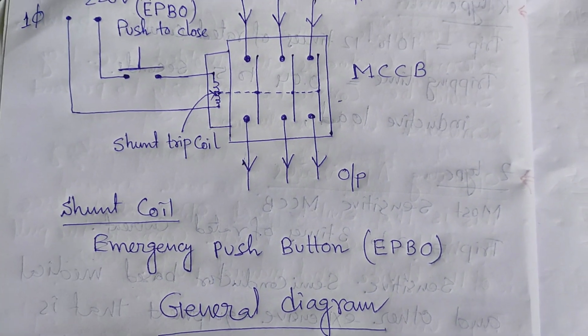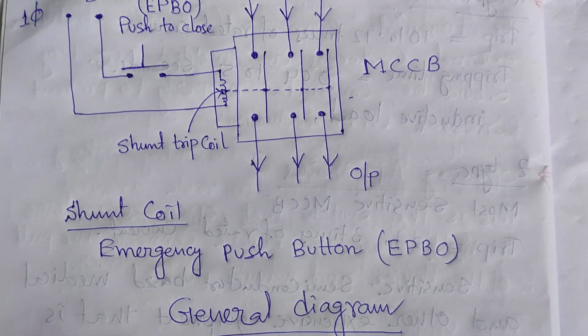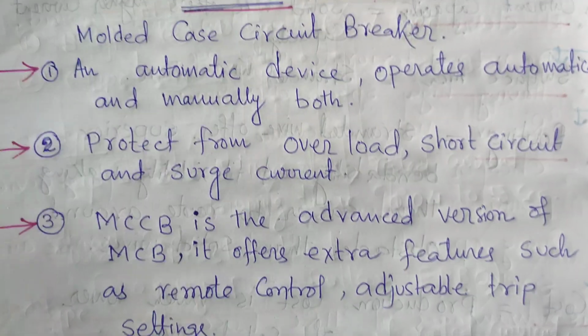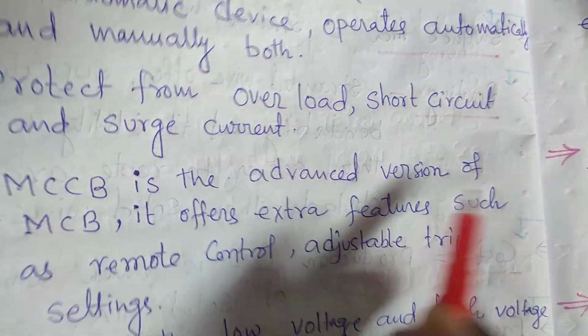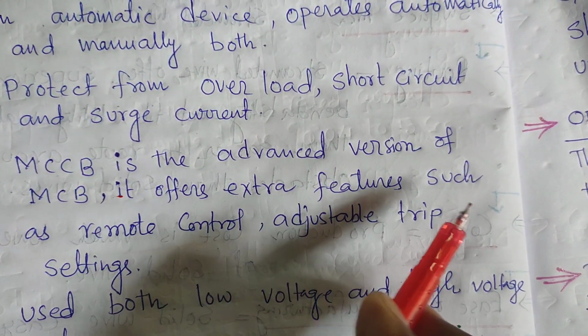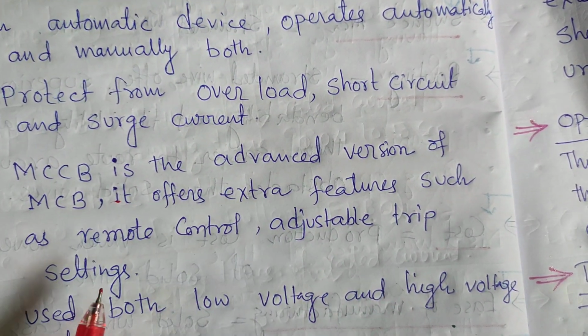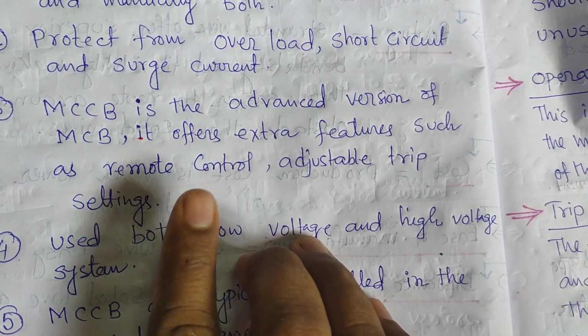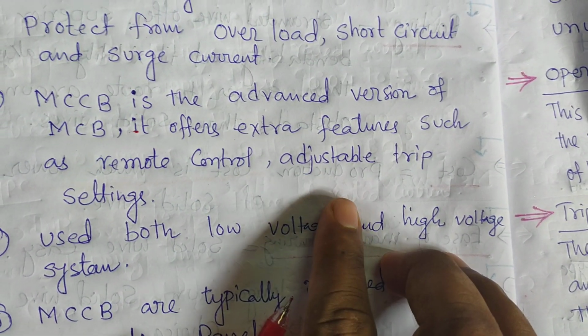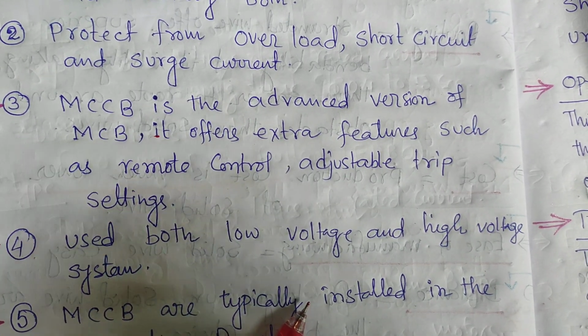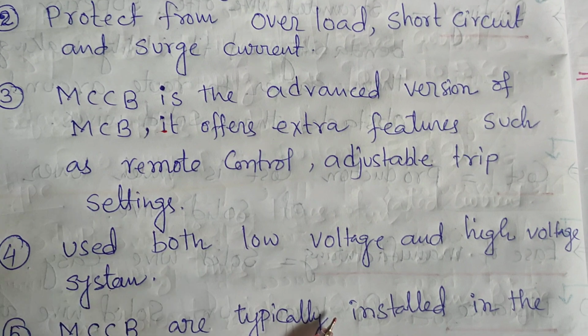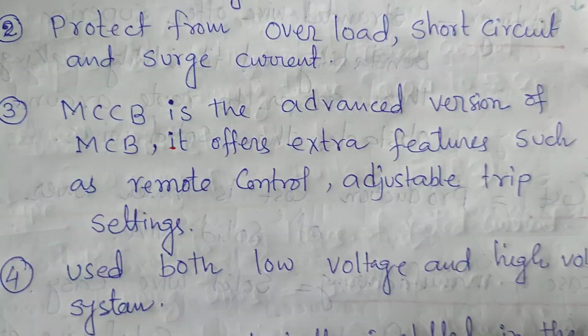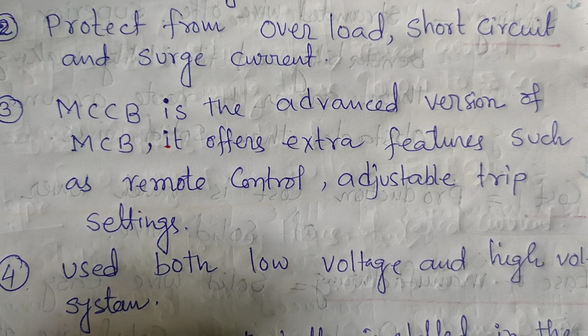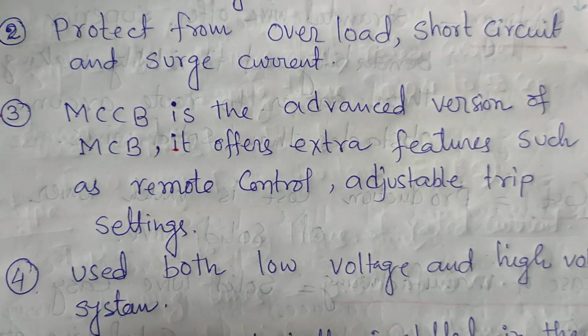Another two advantages of the MCCB: we have discussed that the MCCB is an advanced version of the MCB. It offers extra features such as remote control and adjustable trip setting. It is very important. For remote control, with the help of the shunt coil, we can use remote control operation. And for the adjustable trip setting, there is a notch. I will attach MCCB pictures you can see after my video, showing the adjustable trip coil and the adjustable trip setting.